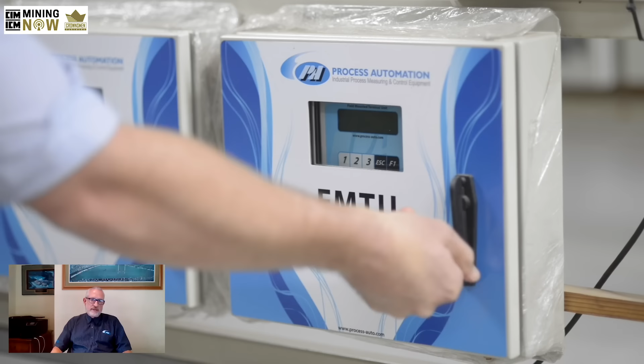In your PLC or DCS, whatever you're using to control your plant, you set up a block and say the speed should be 1.5 meters per second, just for instance. If you see it slipping a little, the only reason is they're over reclaiming, so the control loop backs off the reclaimer, the speed goes back up to 100%, and you've avoided a crisis. That's been the newest development.